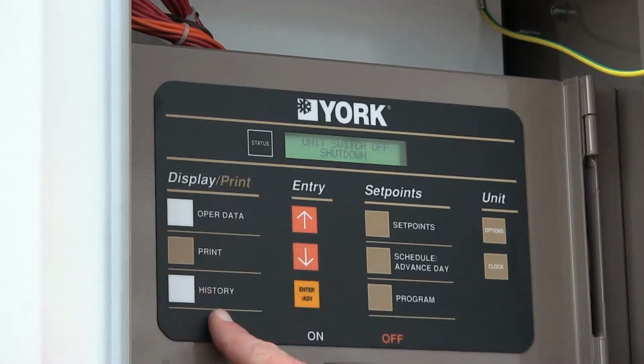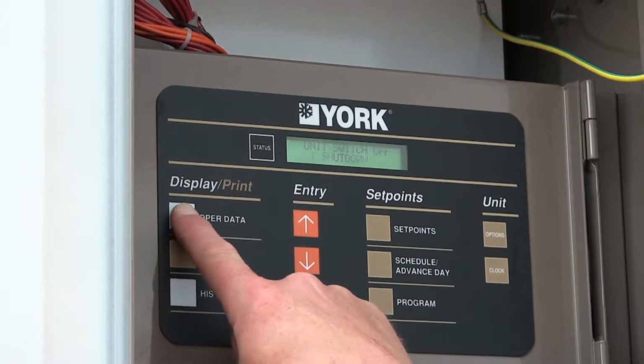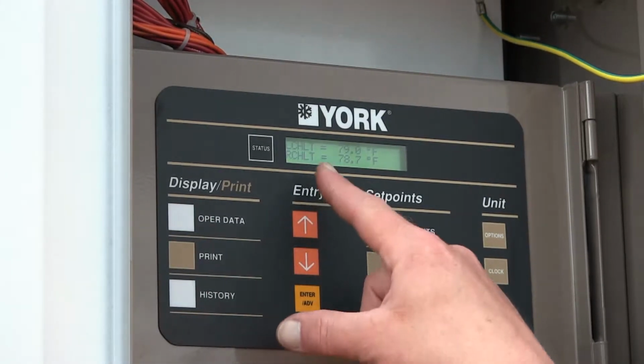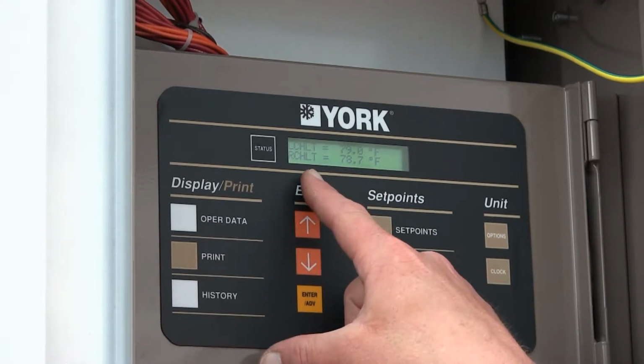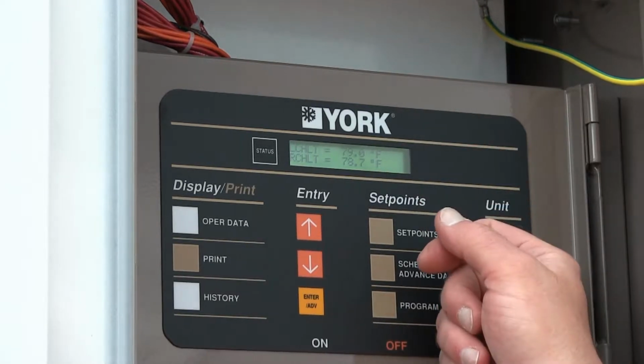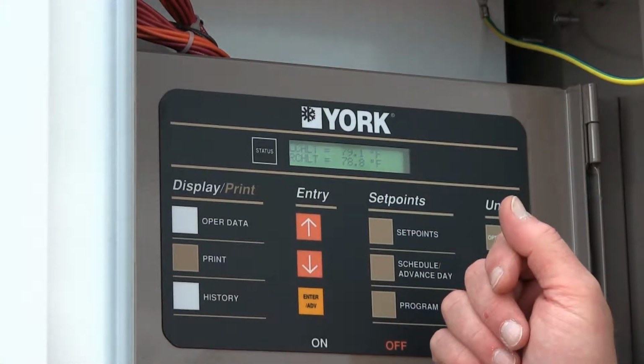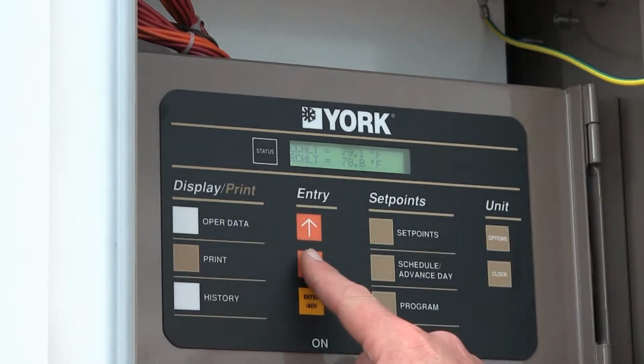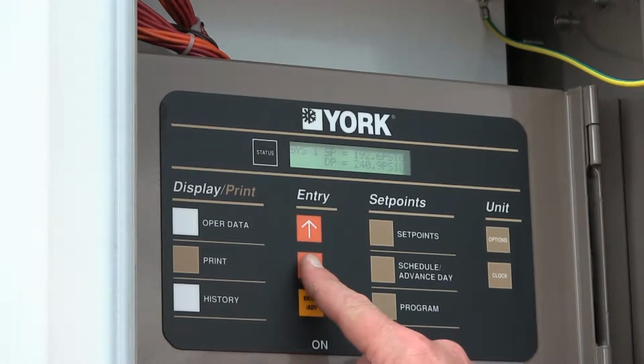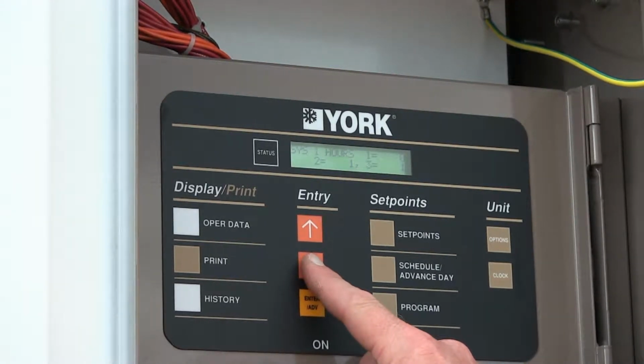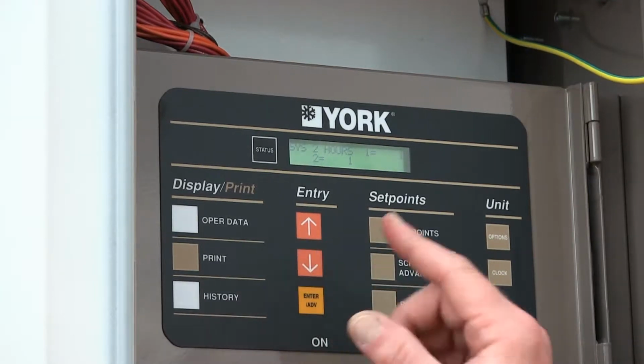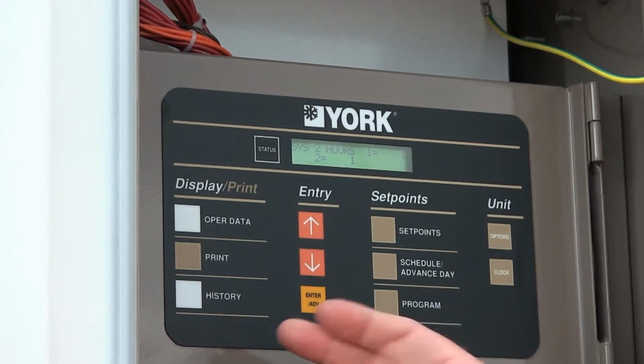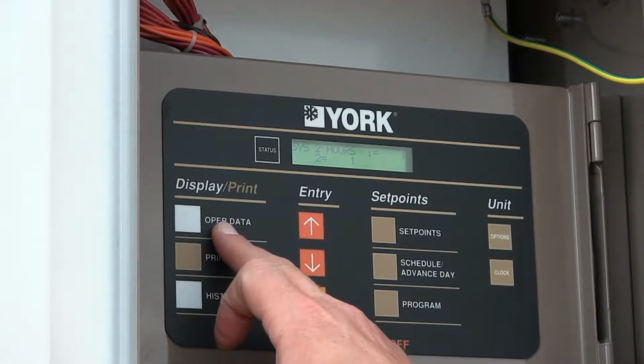So the left side here is operator data. You push it one time, the operator data tells you the leaving chilled water temperature is 79 degrees and the return is 78.7. Notice both those temperatures are similar. That indicates both of our sensors are reading properly. But within that menu, you can see the refrigerant pressures, the temperatures in and out, the hours, the runtime. Again, it's all data on the chiller. There's nothing to be changed under operator data.